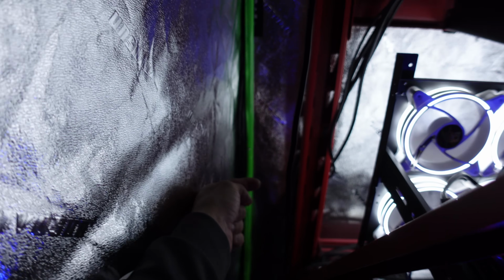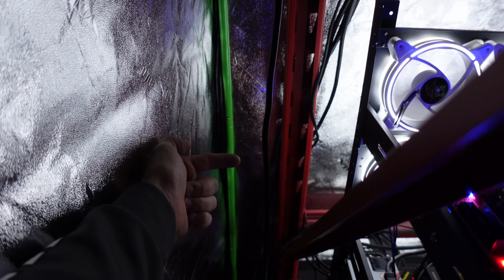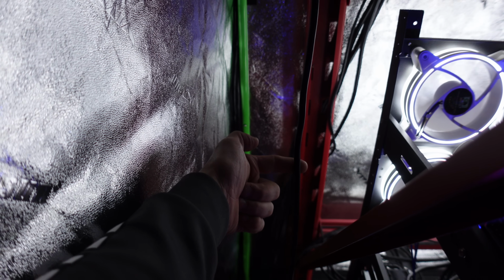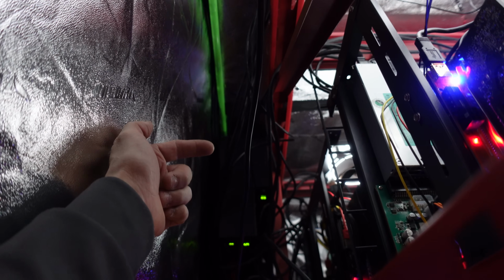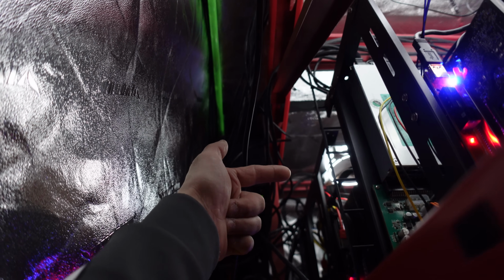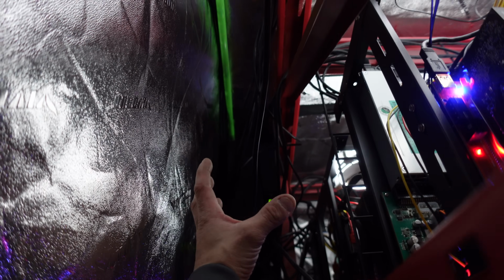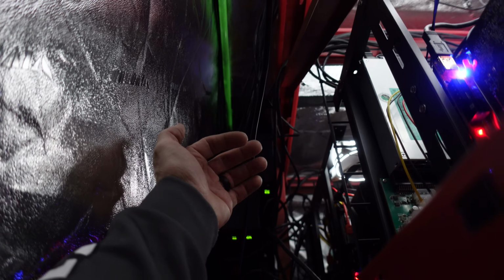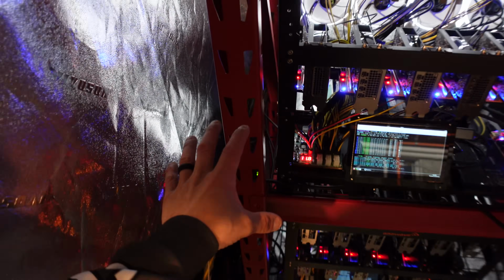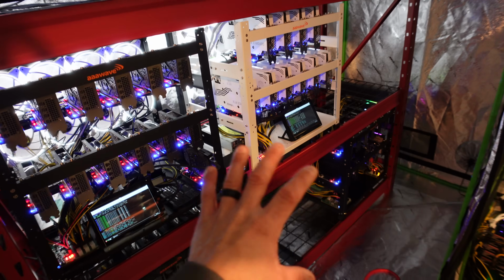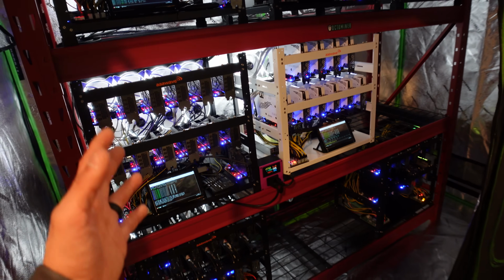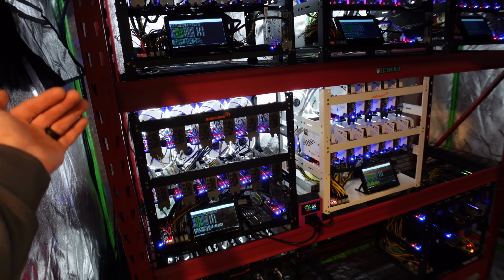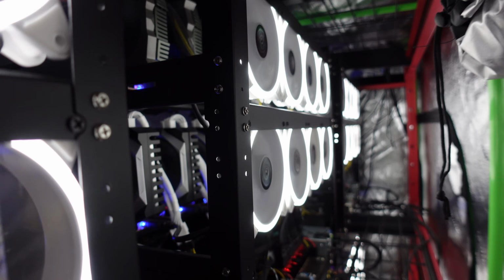Then I'm going to take a T off and feed a piece of smoke pipe in that way, or maybe just leave the T open, who knows. Same thing down at the bottom — feed another T in that way and cap it so it can sit on the floor. I'm going to pull the PDUs forward, and that's going to be my plan for the hot-cold aisle. That's the entire purpose of this — cold aisle on the back side, hot aisle on the front side.